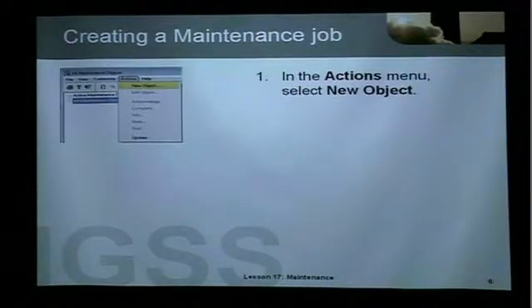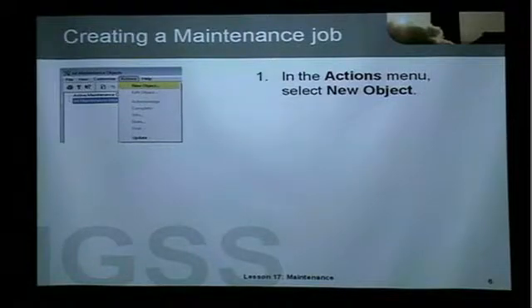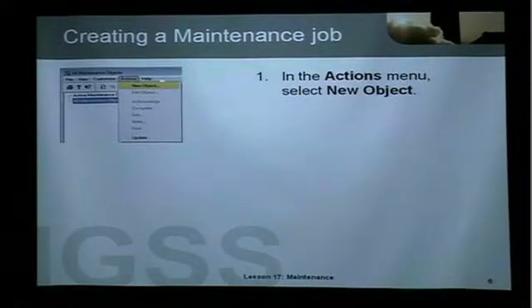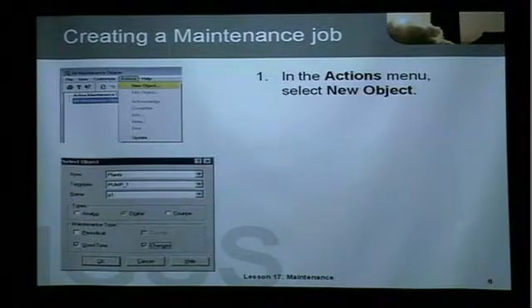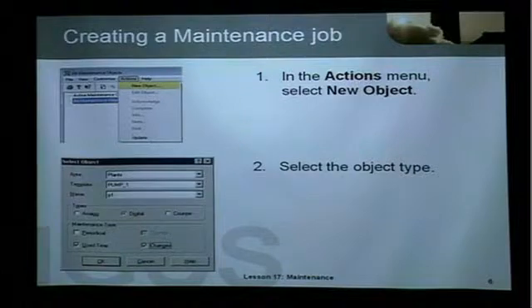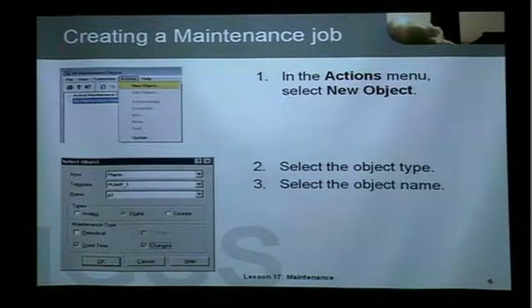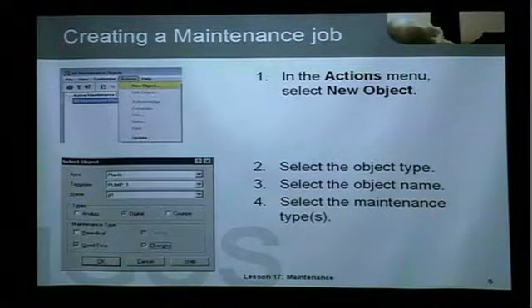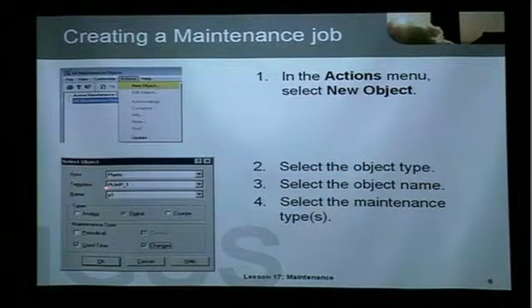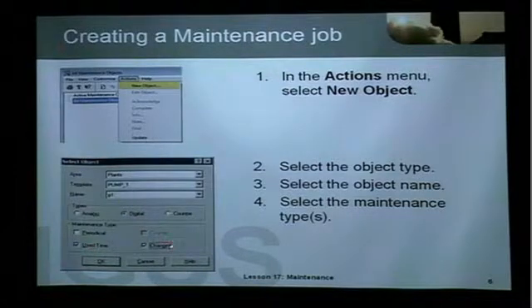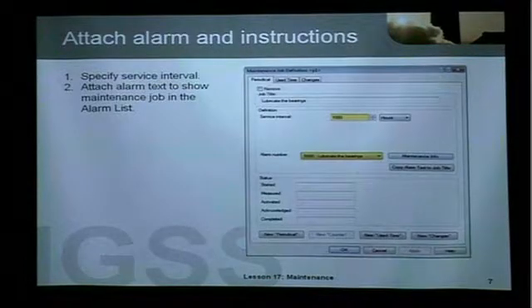How do you create a maintenance job in IGSS? You start the maintenance module — note that the data collection module must be started before you can start this module. You go into the Actions menu and select New Object. Then a dialog box appears where you select the object type, the object name, and the maintenance type. In this case I have selected P1, my pump. It is a digital object and I want to do both use time and changes maintenance, so I have three different options here.